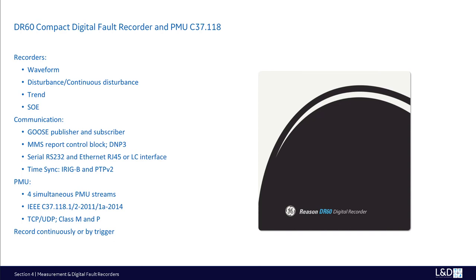DR60 is a natively IEC 61850 concentrated one-box multifunction digital fault recorder DFR and synchrophasor measurement unit PMU. The waveform recorder is supporting 256 and 512 samples per cycle, can be used as a disturbance and continuous disturbance recorder, trend recorder, and sequence of events recorder. All DR60 files, including configuration and logs, are stored in a non-volatile SSD memory. The device removes the oldest records as soon as the mass storage occupation reaches 80%.